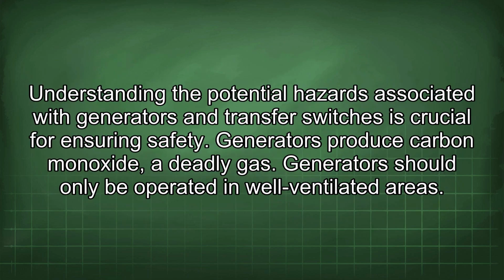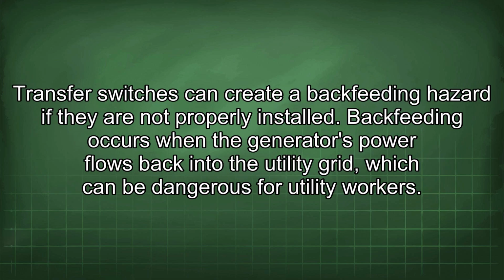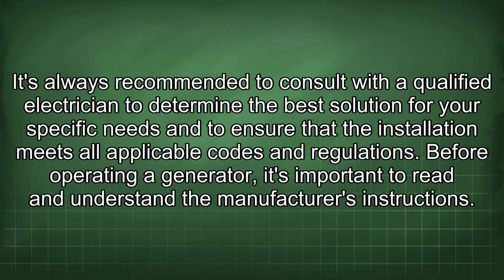Understanding the potential hazards associated with generators and transfer switches is crucial for ensuring safety. Generators produce carbon monoxide, a deadly gas. Generators should only be operated in well-ventilated areas. Transfer switches can create a backfeeding hazard if they are not properly installed. Backfeeding occurs when the generator's power flows back into the utility grid, which can be dangerous for utility workers. It's always recommended to consult with a qualified electrician to determine the best solution for your specific needs and to ensure that the installation meets all applicable codes and regulations.